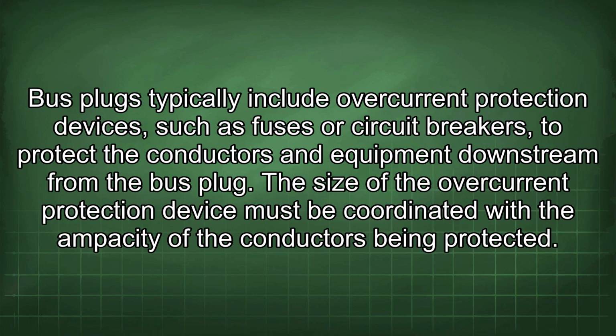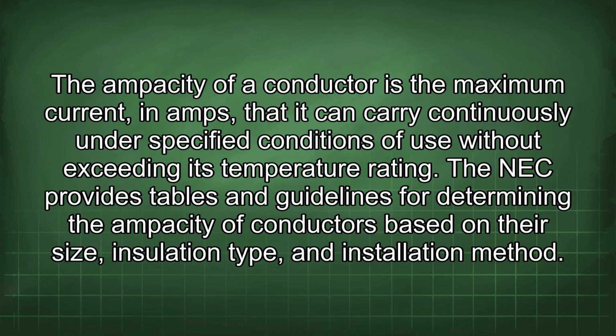Bus plugs typically include overcurrent protection devices, such as fuses or circuit breakers, to protect the conductors and equipment downstream from the bus plug. The size of the overcurrent protection device must be coordinated with the ampacity of the conductors being protected. The ampacity of a conductor is the maximum current, in amps, that it can carry continuously under specified conditions of use without exceeding its temperature rating.